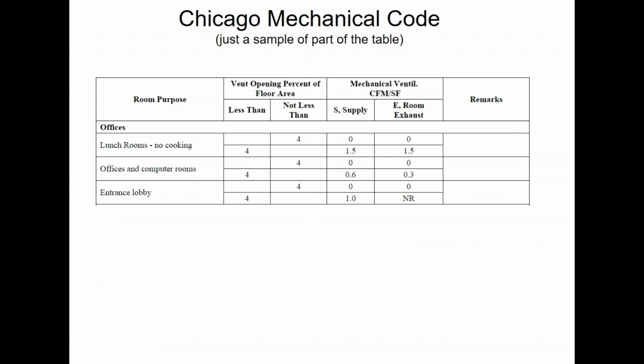Chicago tells you not how much outside air to bring in. They tell you how much supply air to bring into the space, which is completely crazy to me because supply air should be dictated by the load. But they tell you how much supply air to bring into the space.